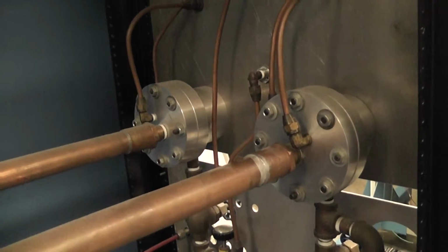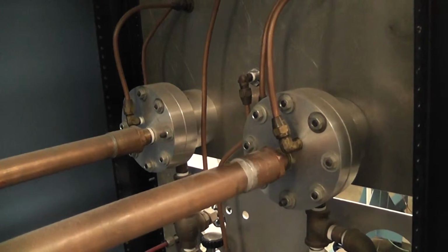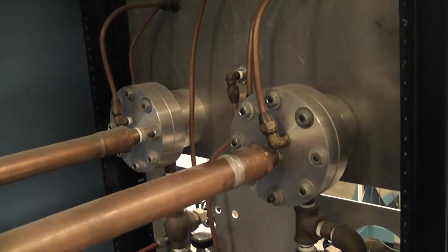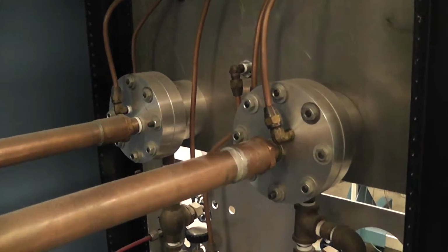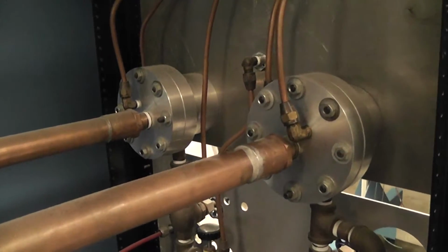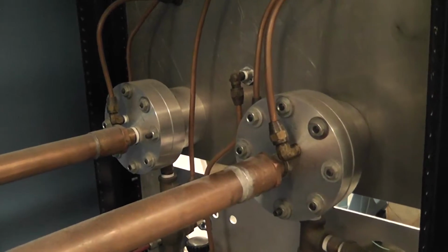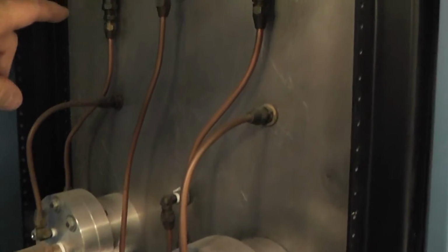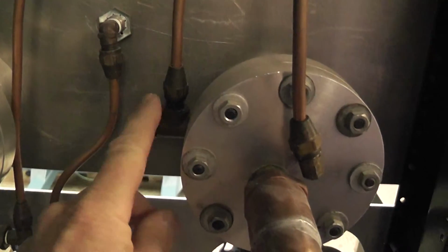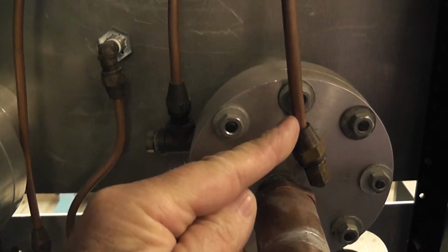Those are the 2 orifice plates, and inside those housings are plates with holes in them that are a certain known size, and it's a knife-edged orifice. In other words, a very sharp-edged orifice. And pressure is read between a static tap and one side of that orifice plate, and you can sort of see that right here. So one side here goes to our gauge, and then this is the other side, okay? And the difference gives you the flow rate across that orifice. And there are 2 of them, both going to the back sides of those gauges there.